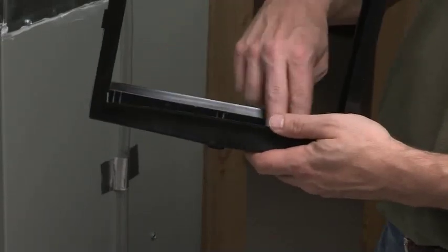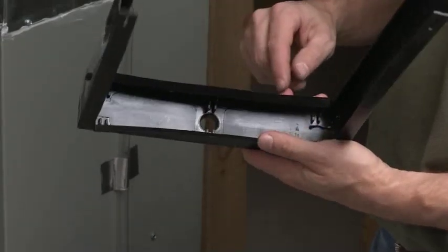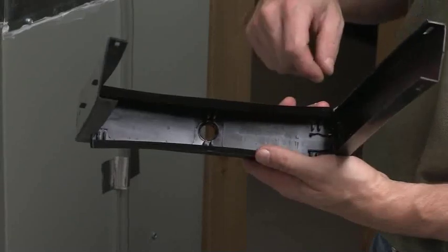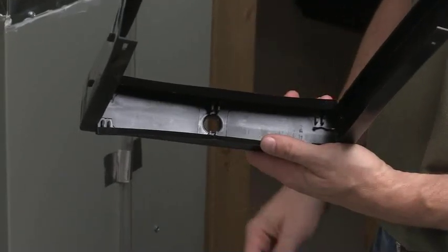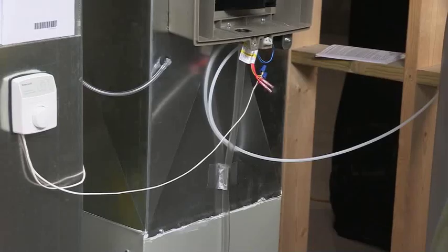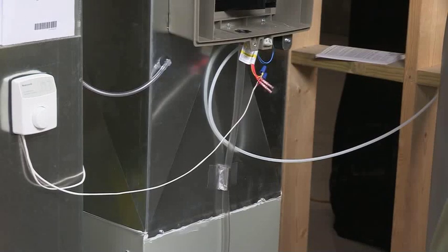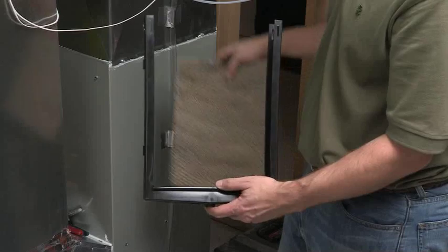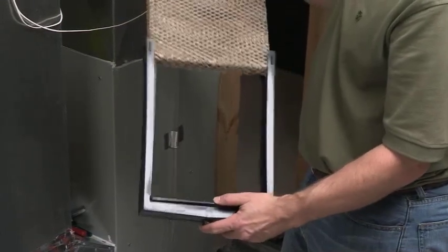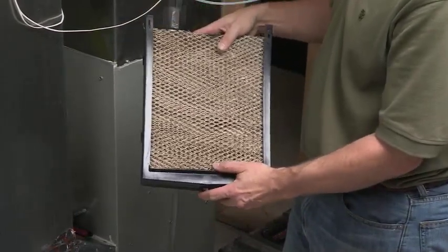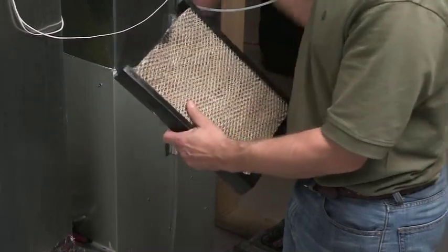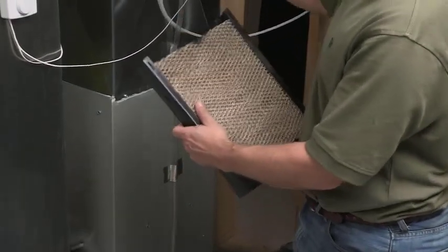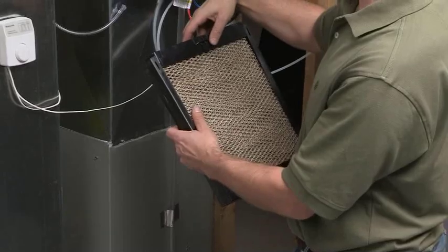Carefully remove any mineral deposits from the tray and the frame. Also, make sure the drain hole isn't blocked. Next, check the drain hose. If you see any mineral deposits, flush the drain hose clean and reattach it to the housing. Slide the new humidifier pad into the frame and snap the water nozzle back onto the tray. Reattach the tray to the frame, then replace the pad assembly and humidifier cover.